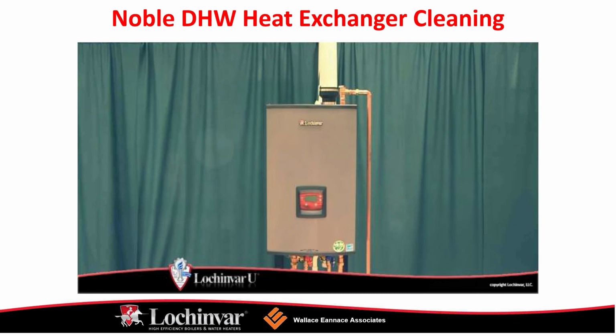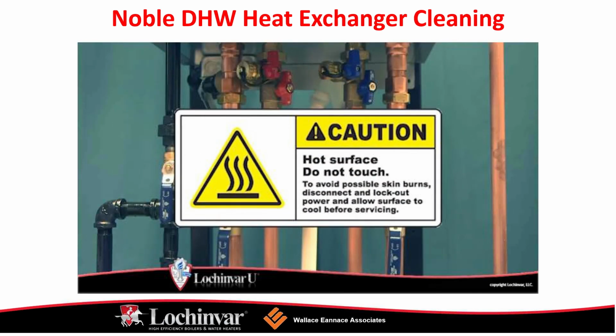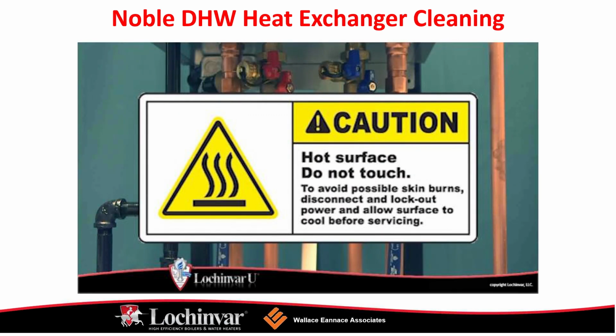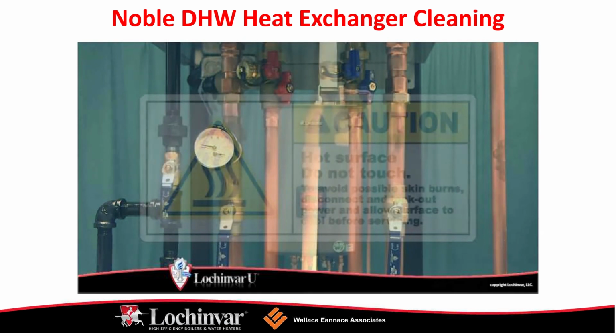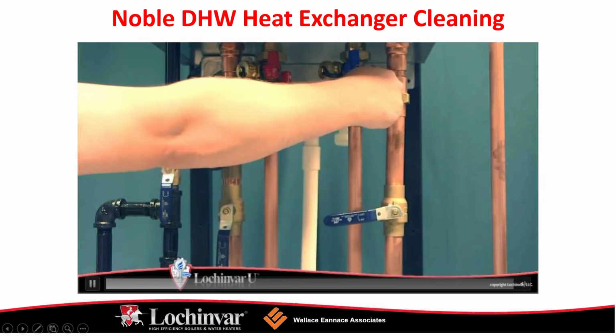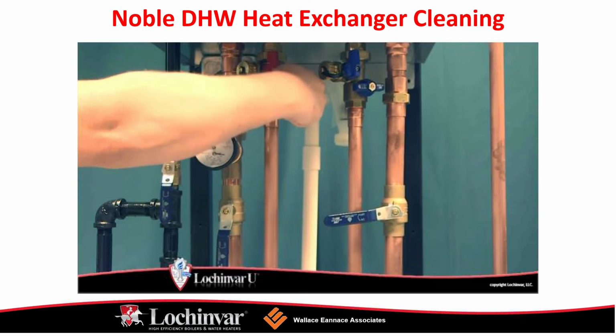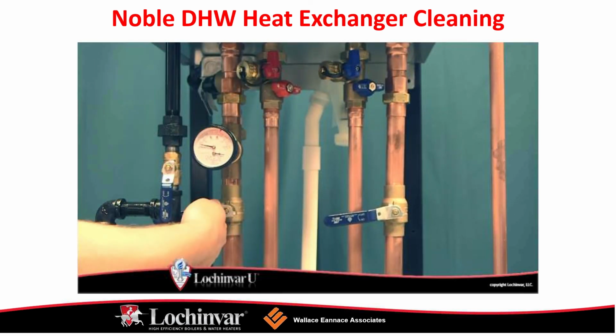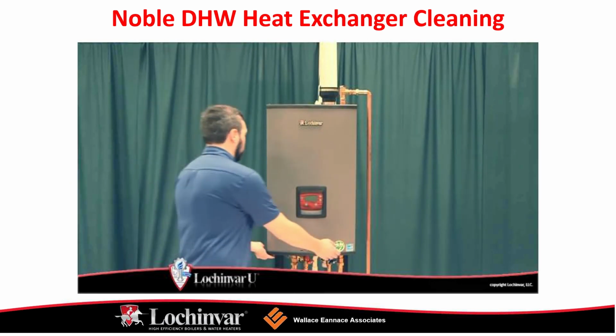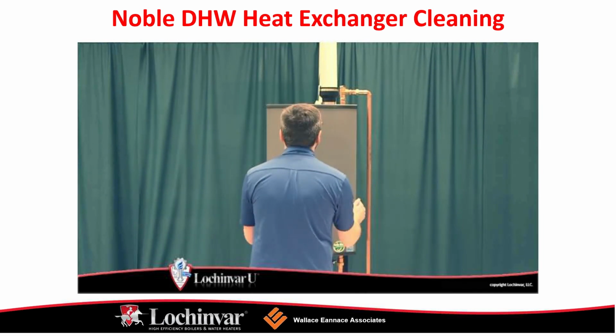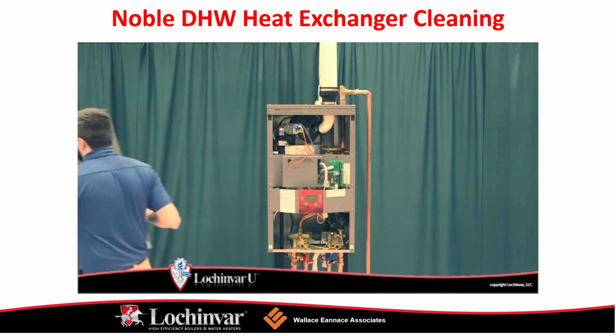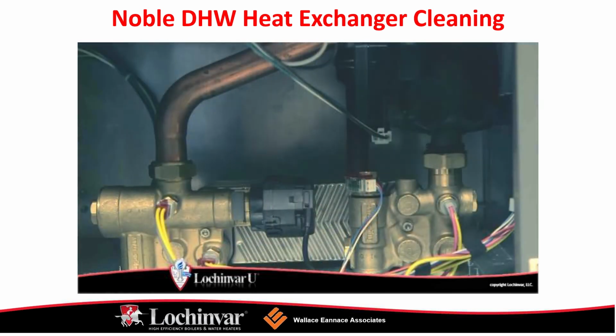Press and hold the right arrow and down arrow buttons simultaneously for 5 seconds. A wrench will appear on the status line of the display. The unit will fire at its normal ignition speed and will then modulate its firing rate to 100%. During service mode, the control will ignore all other heat demands. However, all safeties and maximum set point temperatures will be active.